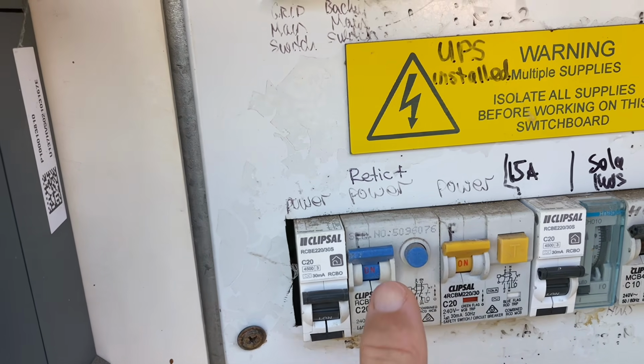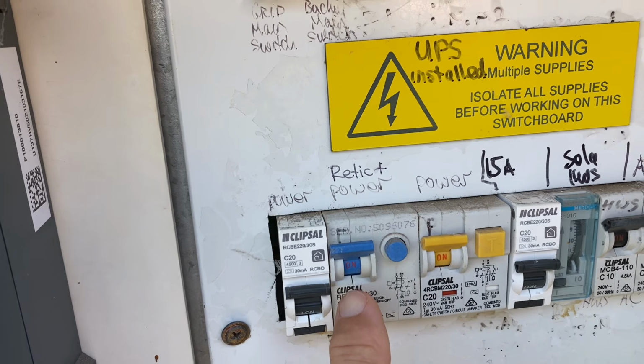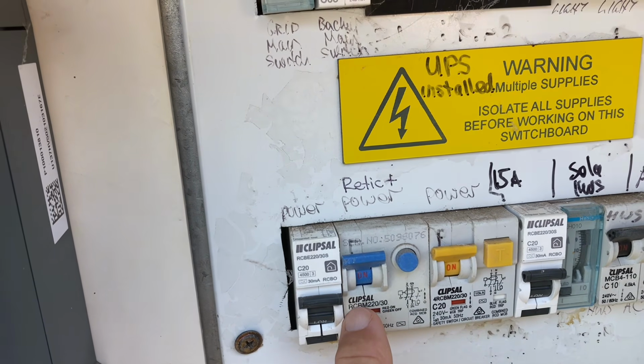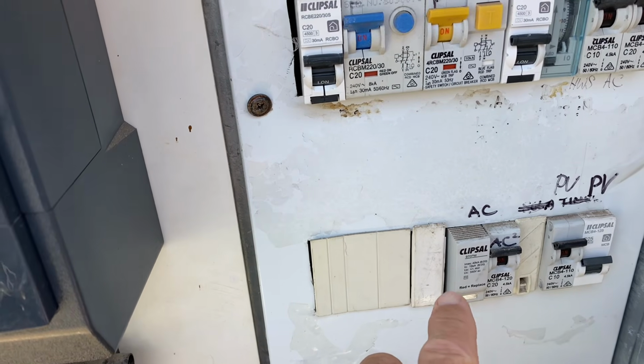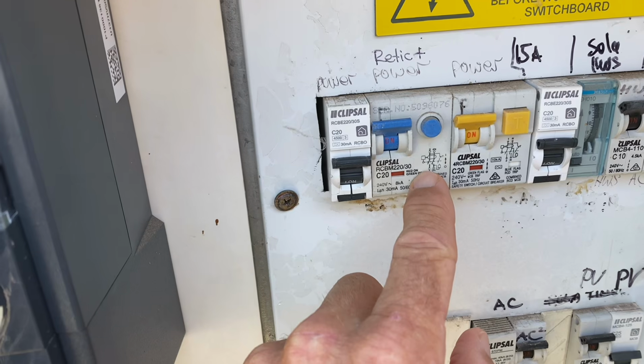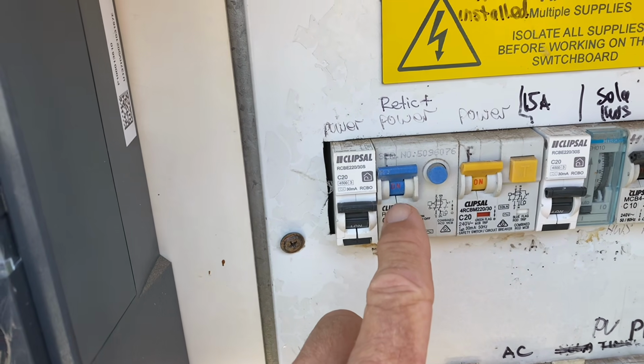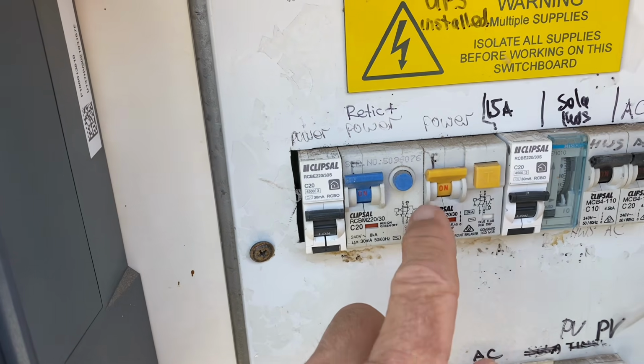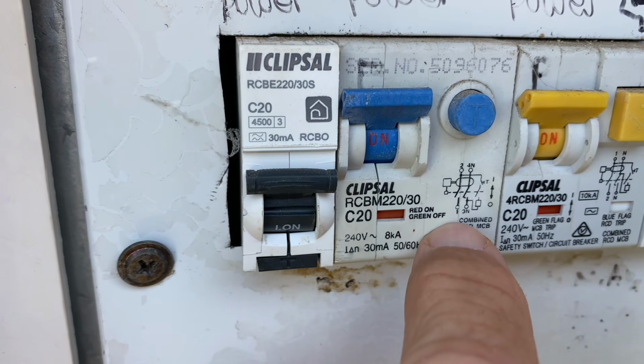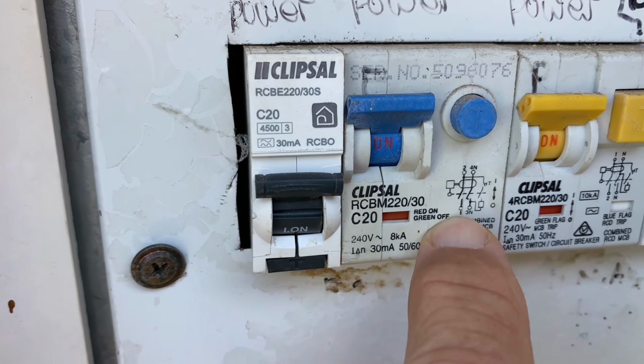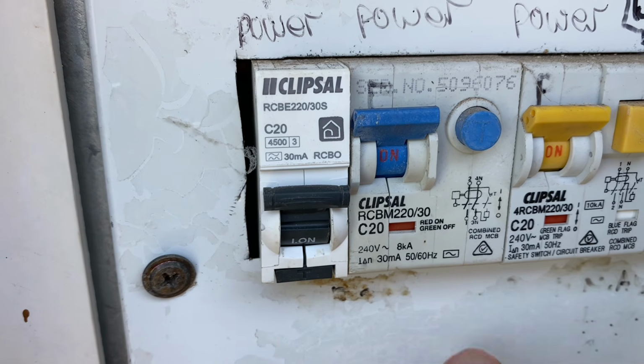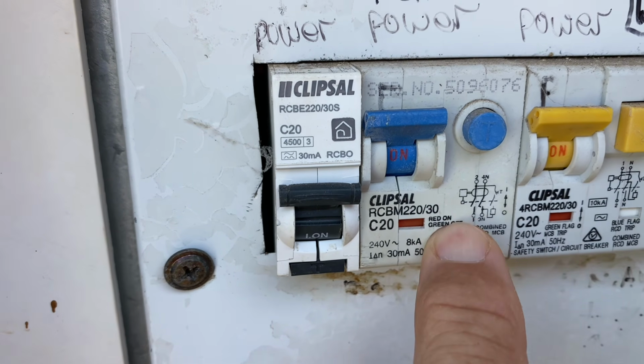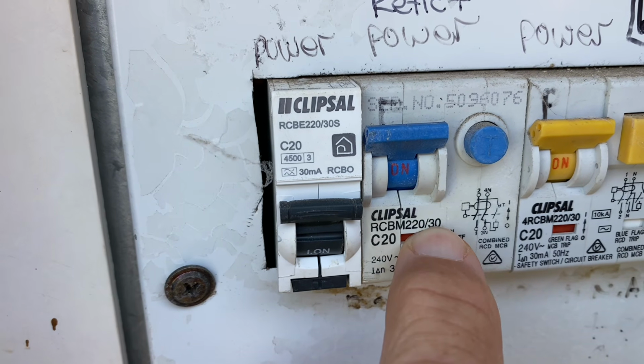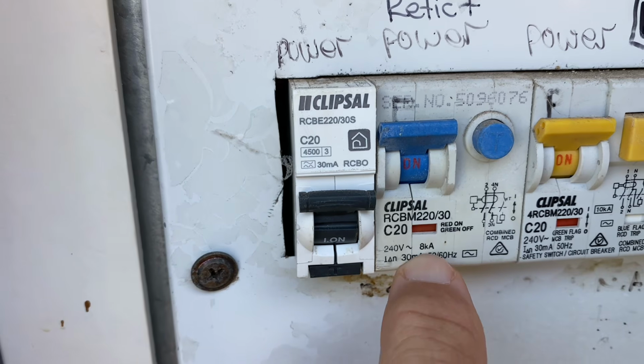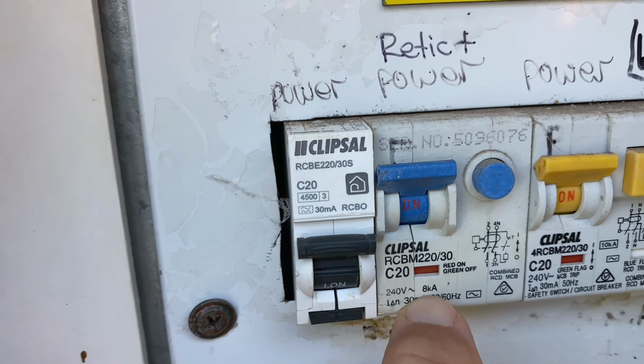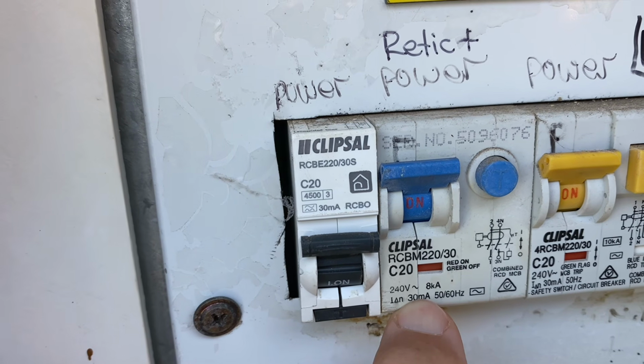And how the RCDs work is they measure the amount of power or current going into the circuit, and then it'll have its loads, and then the amount of power going back through the RCD. So it's measuring the current coming into the circuit and the current coming back out of the circuit. As you can see there, they are a double pole device, one pole active and one pole neutral. Now if there's any differential between what went into the circuit and what came out, it knows there's potentially an earth leakage of, for this one, 30 milliamps, and then it will trip. That there is its fault current rating, 8 kA, and that's our tripping amount for the earth leakage.